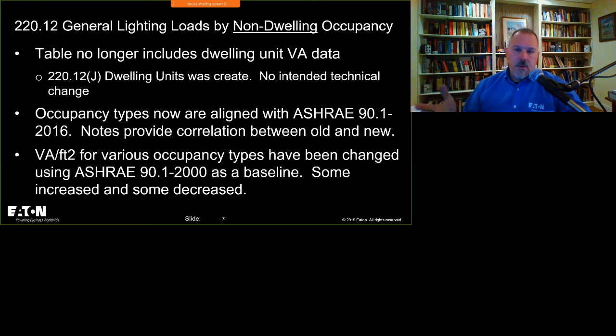The issue that we came across was similar to what we find with the National Electrical Code. The ASHRAE requirements are not accepted and adopted across the country as soon as they come out. So there are states that are on older versions of these ASHRAE requirements, and there are states that are on newer versions. And I could argue that there are states that aren't on any version of these ASHRAE requirements. But suffice it to say, most of our design engineers are designing structures and commercial buildings to meet some level of these ASHRAE requirements. We didn't want to get very aggressive with the low VA per square foot, well, watts per square foot, but you have to convert that to VA. We'll have a discussion about that later.